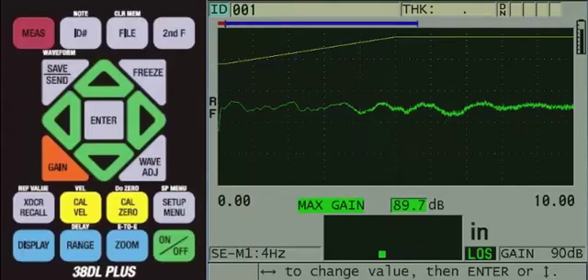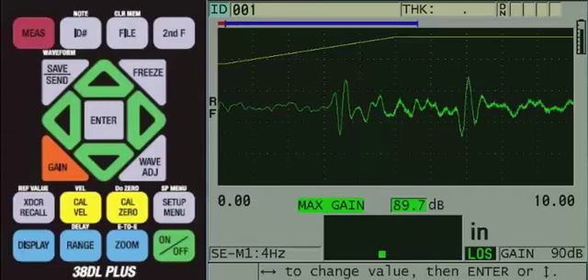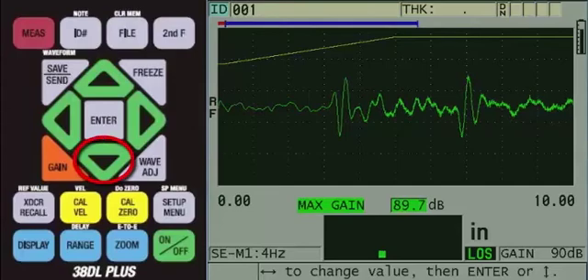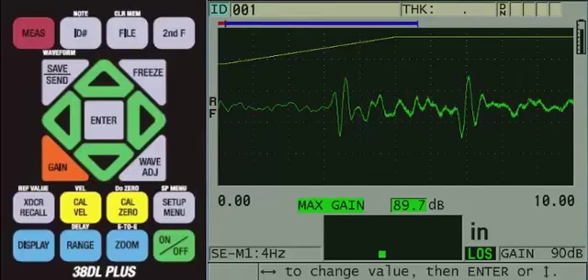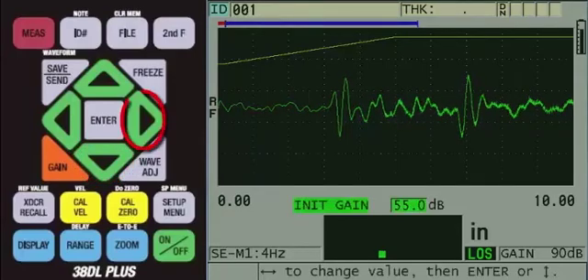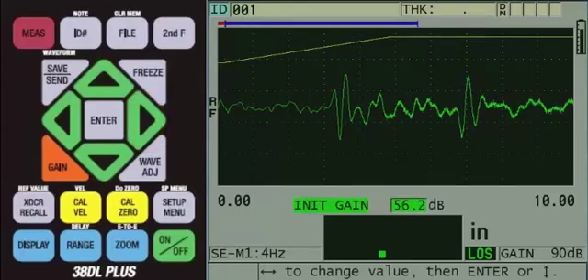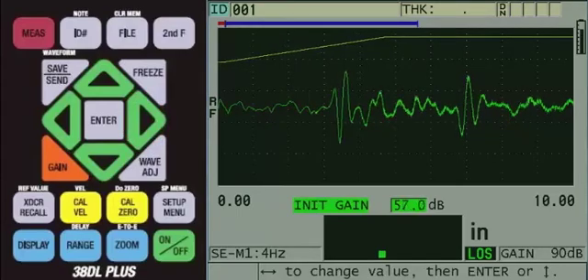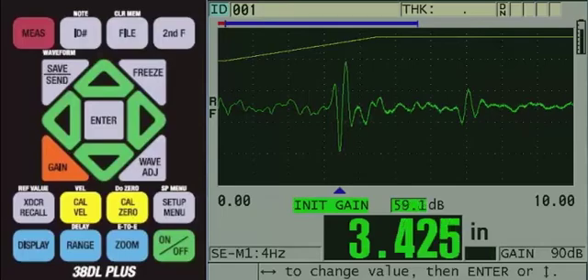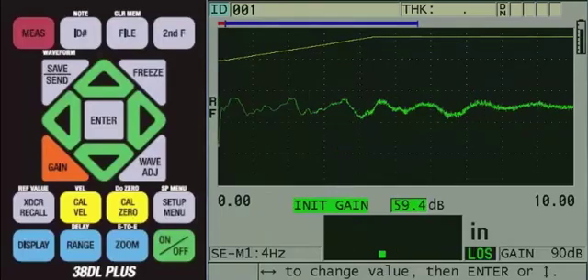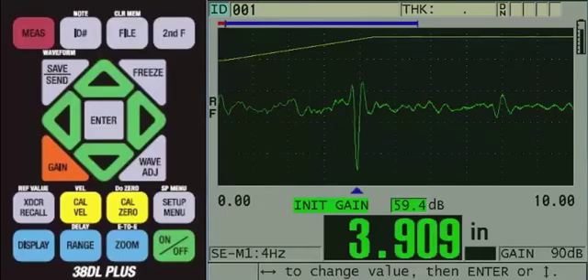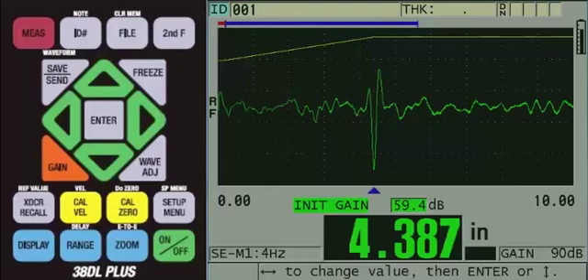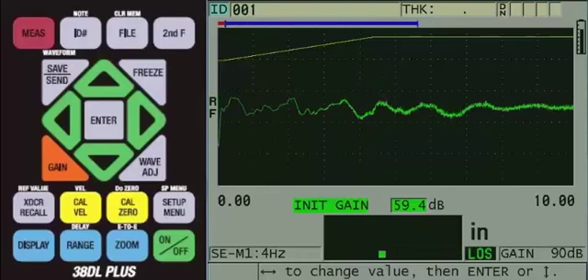When we get to the thinnest step, the back wall echo is not being detected. Since this echo appears sooner in time, use the arrow keys and go to INIT GAIN, then use the right arrow to slightly increase it until the back wall signal from the thinnest step is detected. After making this adjustment, it is a good idea to check the other steps again to make sure they are still able to make detection of the back wall signals.